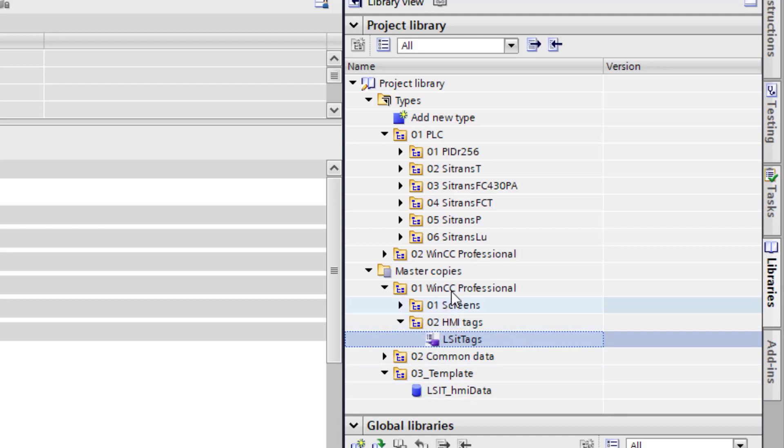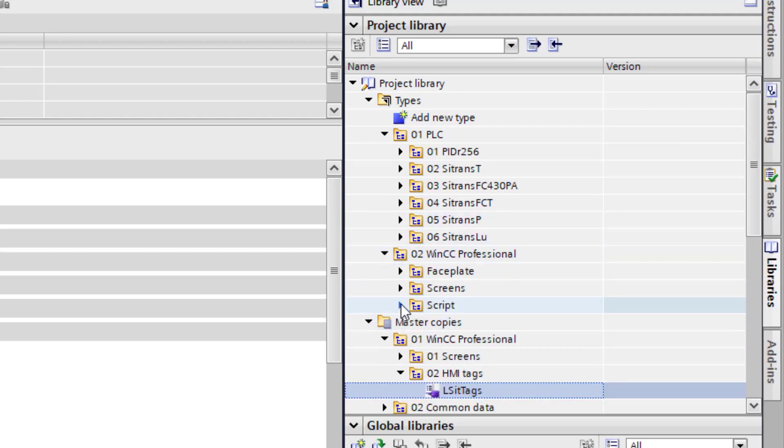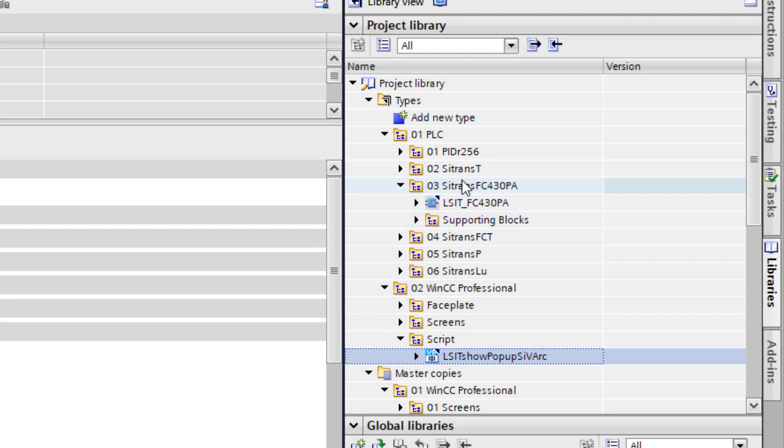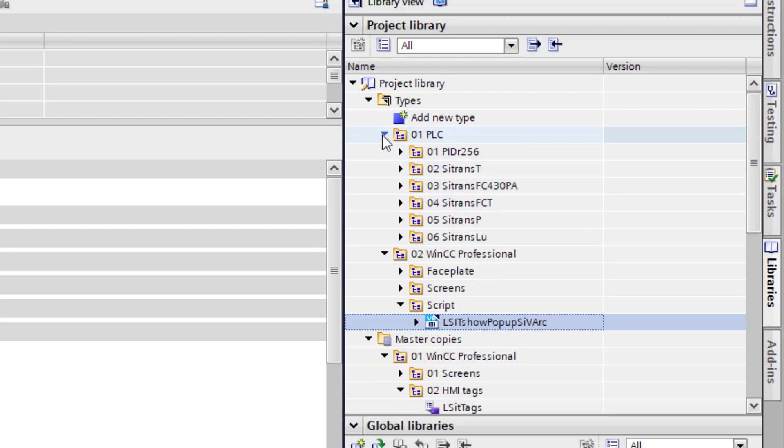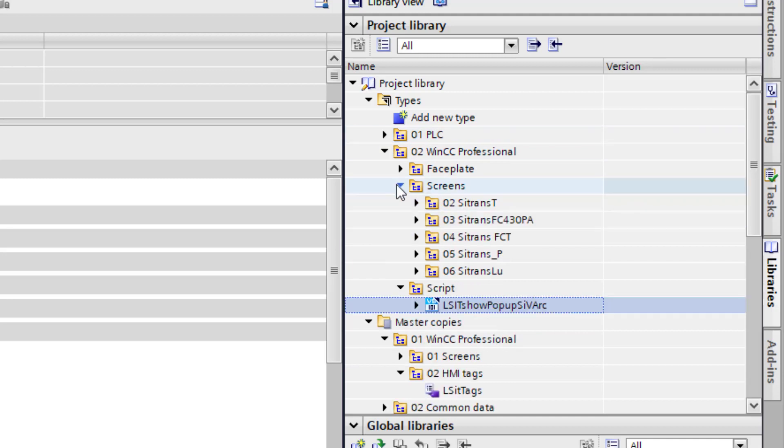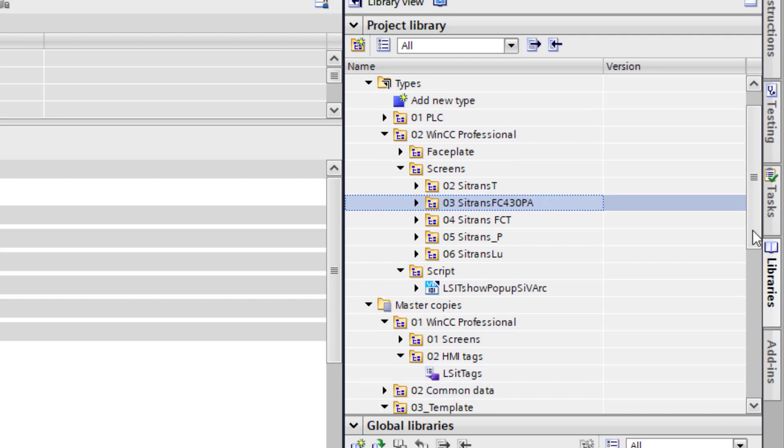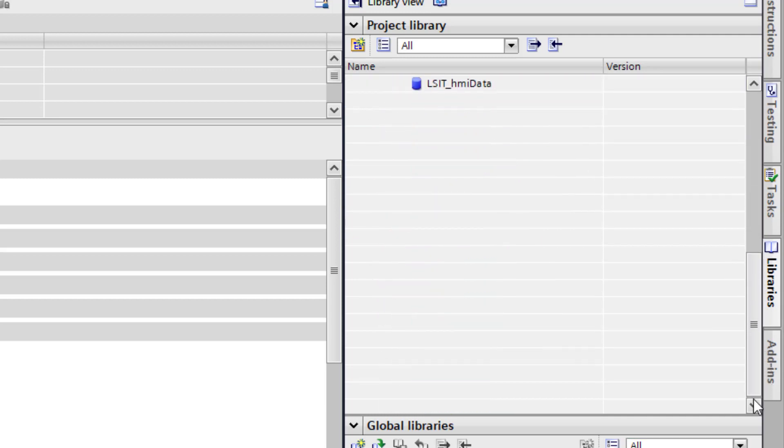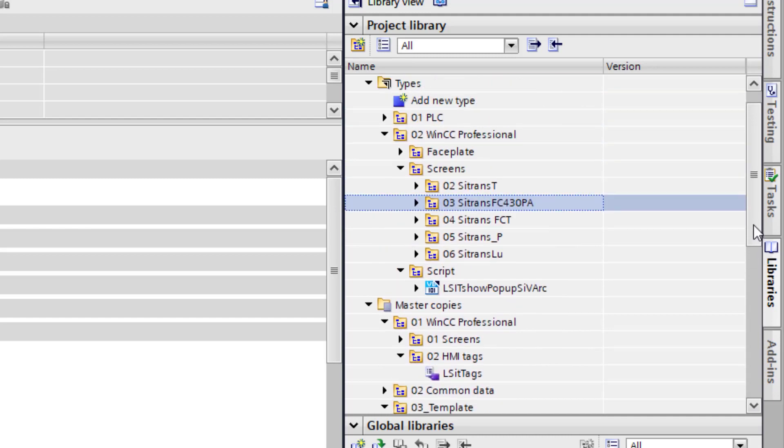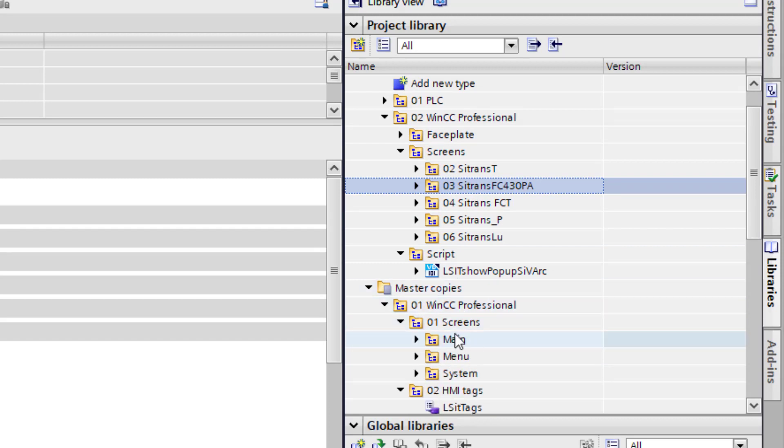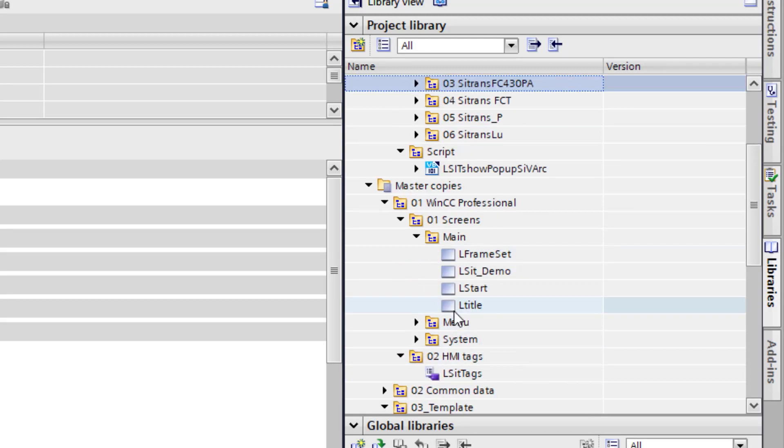I will touch base on those in a minute. And then under WinCC Professional you have got your script. So we need to bring in your Visual Basic script. And then your folder with your faceplates in. So if we go to screens there we have the FC430PA. So drag that whole folder in, there are multiple screens underneath there and put those into your project. If you are using the example project for the first time. You need to set your theme to WinCC Light.